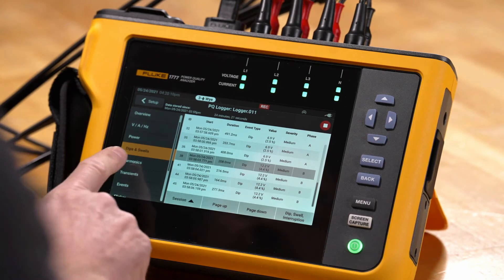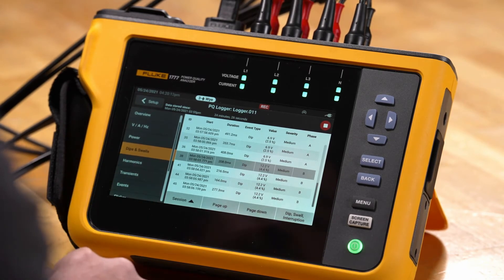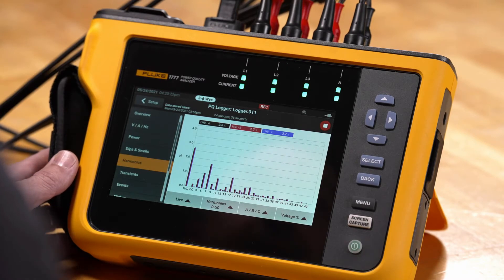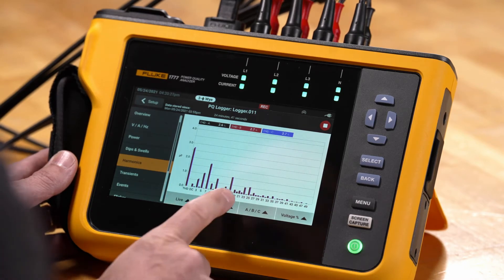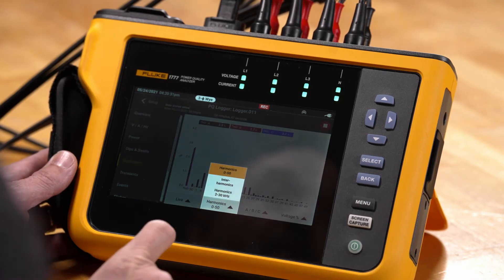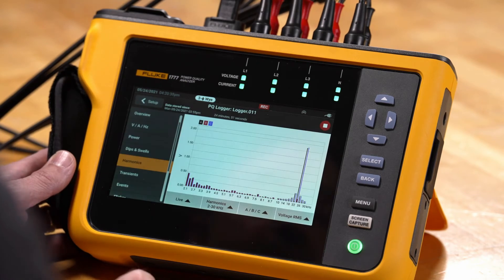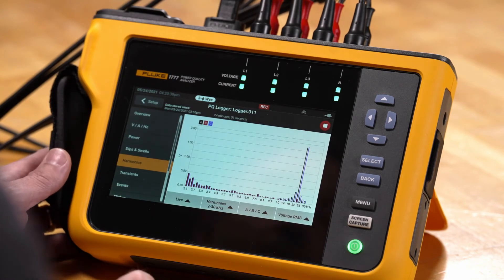We also have the ability to look at harmonic data. Harmonic data lets us look at the harmonics as a bar graph, and we can break it down phase by phase or look at all three phases simultaneously. One of the advantages here is we've added not only interharmonic data but also supraharmonic higher frequency data, so if somebody wants to view higher frequency harmonics, they can see those as well.